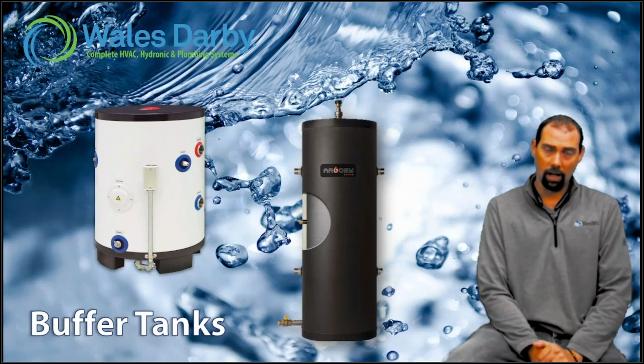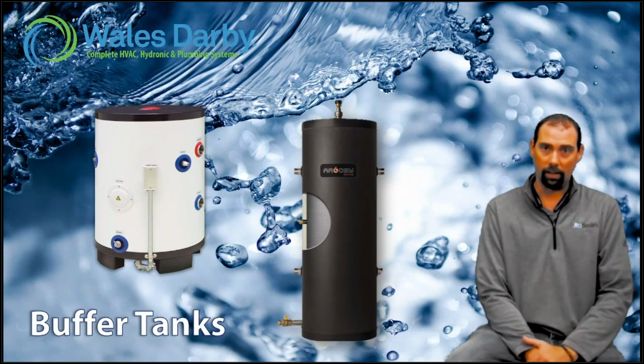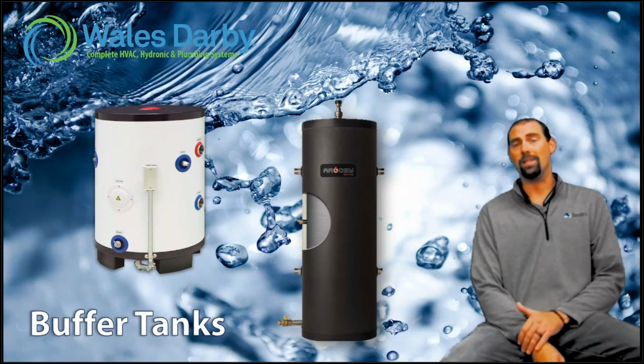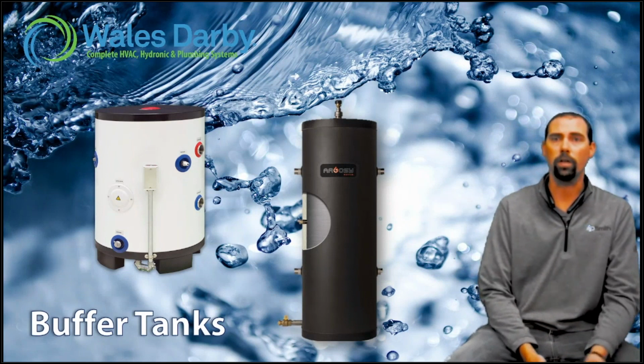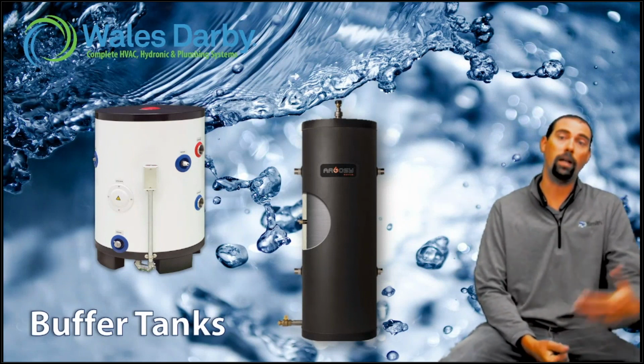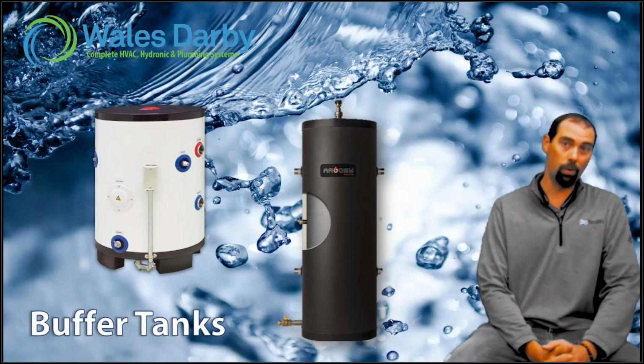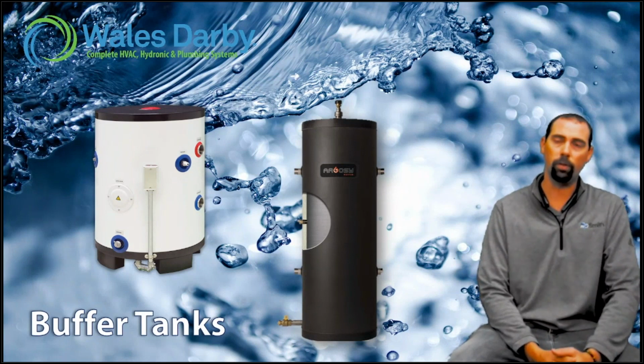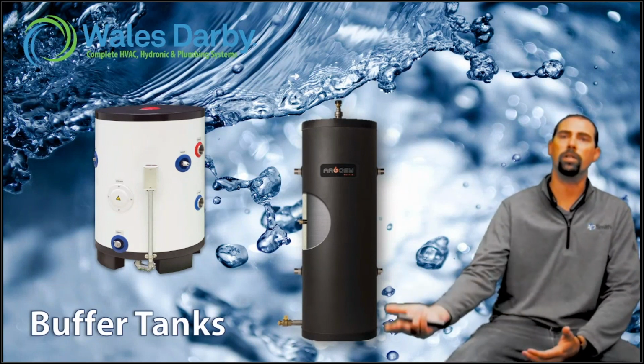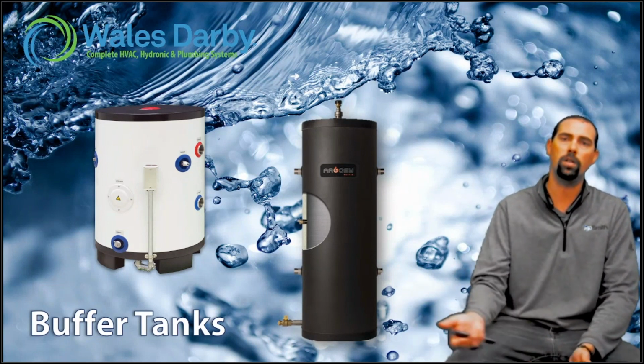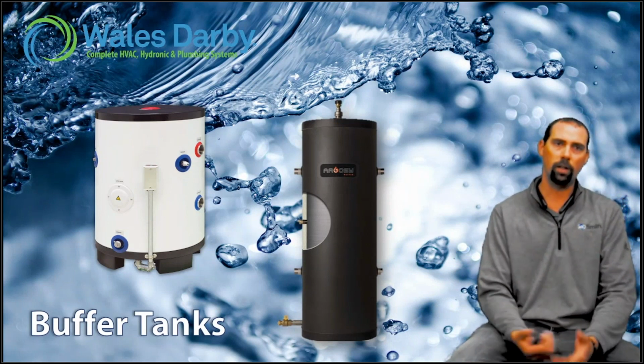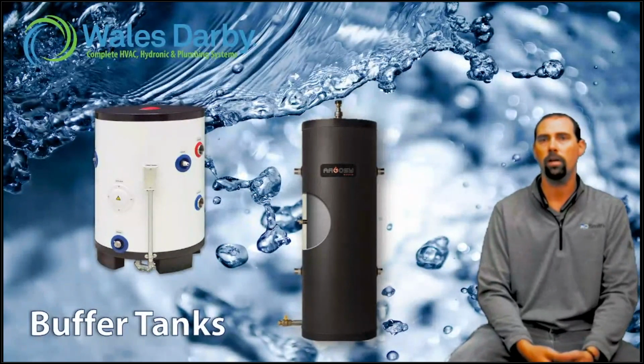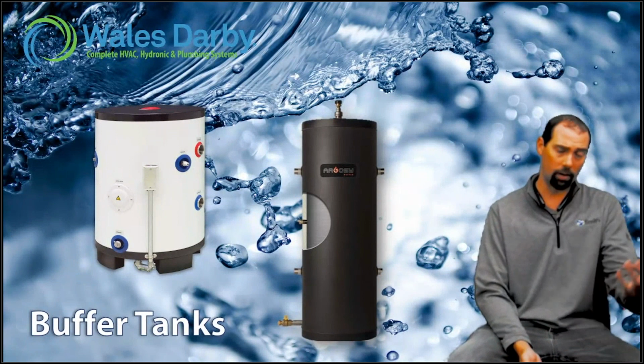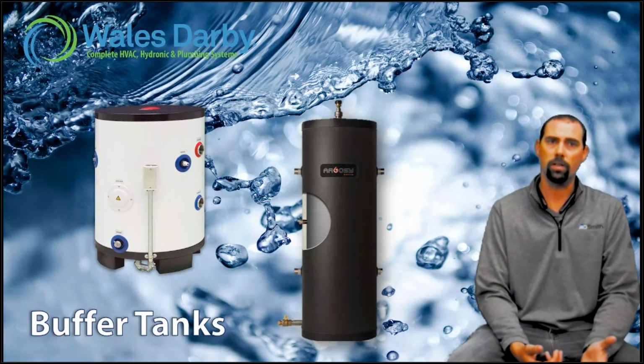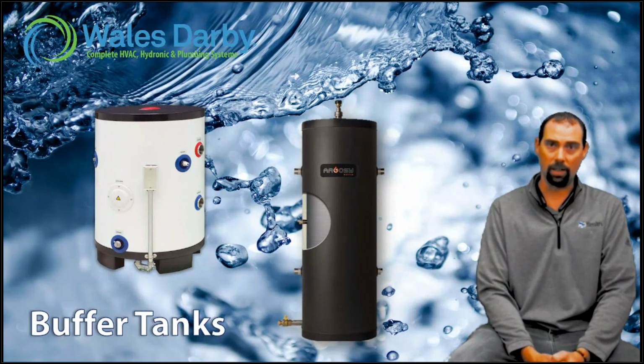Another thing I like to say about buffer tanks is it's always cheaper to buy the storage than it is to buy a second outdoor unit and put that on the side of the house. Do we want a second storage tank to store more BTUs instead? That depends on the application, space in the mechanical room, and so on, and all of that comes into consideration when we start sizing buffer tanks.